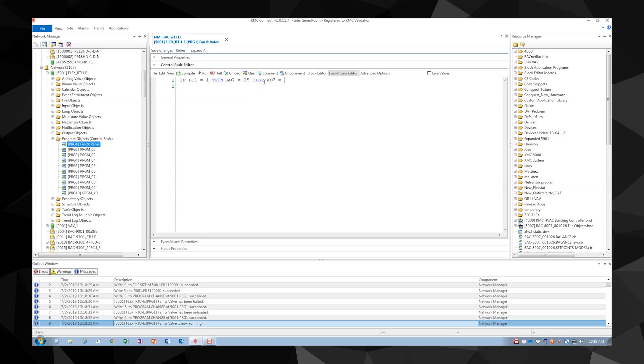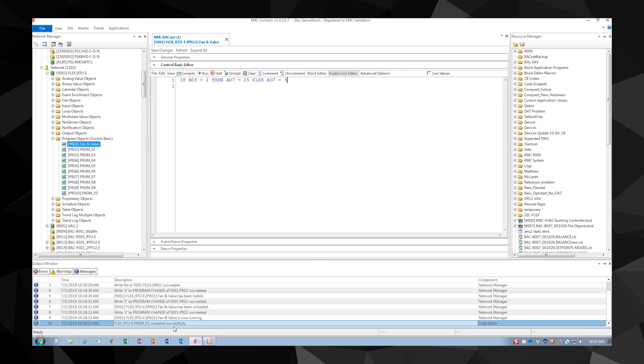Let's add an else A07 equals 5 to the end of our code. Now our code is going to read if B01 equals 1 then A07 equals 25 else A07 equals 5. The else syntax is saying if B01 is not equal 1, meaning the fan is off, change our valve position to 5.